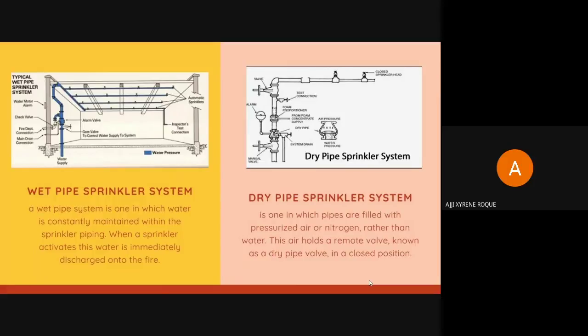increased value. So sa Philippines, as engineers, alam ba natin kung ano yung usual or ano yung common na ginagamit na sprinkler systems? And ano-ano yung mga kino-consider sa pag-i-install nito? According to the National Building Code of the Philippines, Presidential Decree 1096, Chapter 12, Section 1204B, automatic sprinklers shall be provided around the perimeter of the opening and within a 600 millimeters of draft curtain. The distance between sprinkles shall not exceed 1.8 meters center to center. Therefore, ang common na ini-install sa ating houses or sa ating buildings dito sa Philippines are automatic sprinklers.